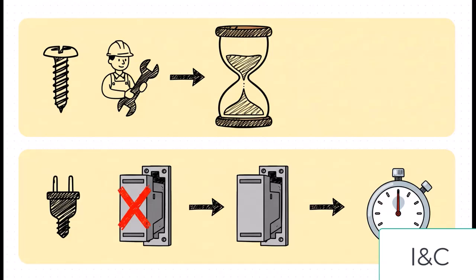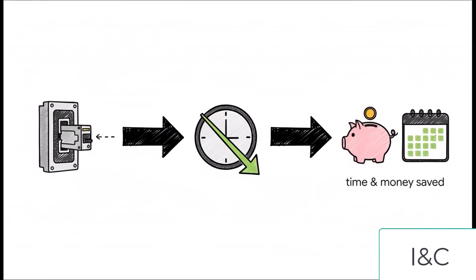With a fixed breaker, you have to power down the entire panel, send a technician in to manually unbolt the unit, disconnect everything, install a new one, reconnect all that wiring, and then re-energize the whole system. We're talking hours of downtime. But with a withdrawable breaker, you use a special tool to rack out the faulty unit, which safely disconnects and pulls it out. You slide in a spare and you rack it back in. Power can be back on in minutes. So what's the bottom line here? It's pretty simple, really. This one architectural choice has massive consequences. For something like a data center or a hospital, a few hours of downtime can mean millions of dollars in losses, or even worse, it could put lives at risk. The withdrawable design is an elegant and powerful solution to that very, very expensive problem.